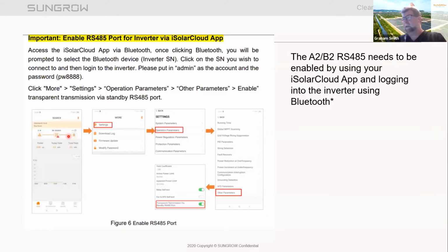Now you'll also have to enable, on the inverter, if you're using an IM4 dongle, the inverter that has the meter connected to it, and we will produce an actual document on this so that you've got it. You do have to enable the RS485 port for the meter. Now, I'm not going to go through that, but you go into the settings from the Bluetooth once again. You go into the parameters, and you'll just enable this. It's called transparent transmission via standby RS485. And you just do that and it will be enabled.